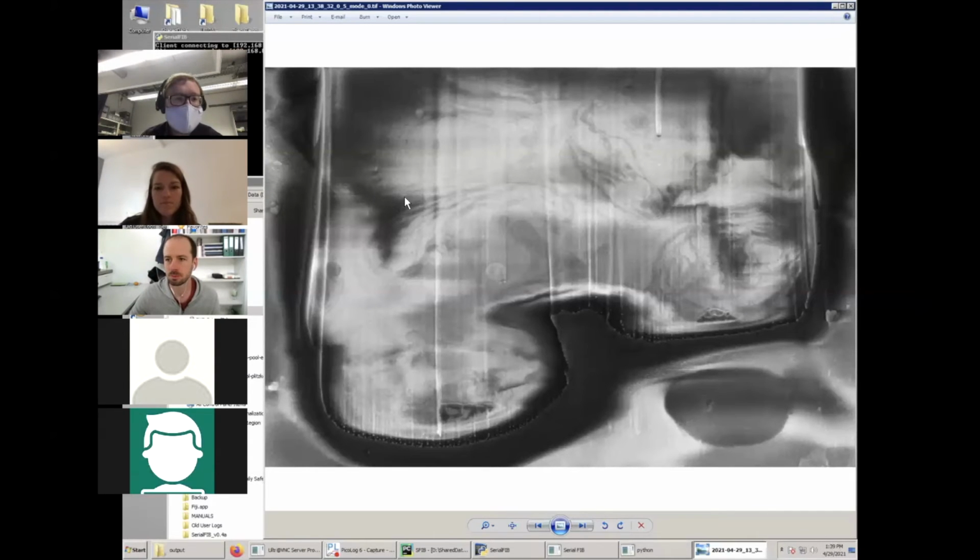Yeah, so dose we're not quite decided yet. But dwell time I can definitely tell you. So dwell time at 13 picoamps is something like 0.25 microseconds and then a line integration of 64. So 64 times 0.25 at a pixel size of 3.8 nanometers was usually, when you take two images at that, it starts bubbling. So I assume that's the region where things get messy.